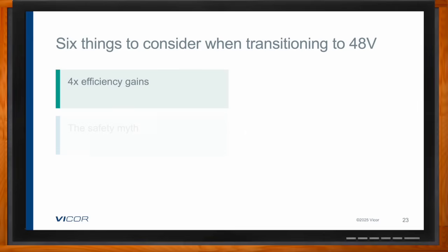The next point is the safety myth. One reason 12 volts is popular is because it's a very safe voltage, but 48 still falls into the safe voltage range, and it actually goes as high as 60 volts, with 48 volts being the midpoint. A lot of our inputs are around 48 volts, 40 to 60, because depending on the source it's never going to be exactly 48 volts in the real world. The safety myth is people thinking it has to be 12 volts to be safe, but no, 48 volts is also considered SELV, which is why it's been adopted in many industries, as I mentioned.